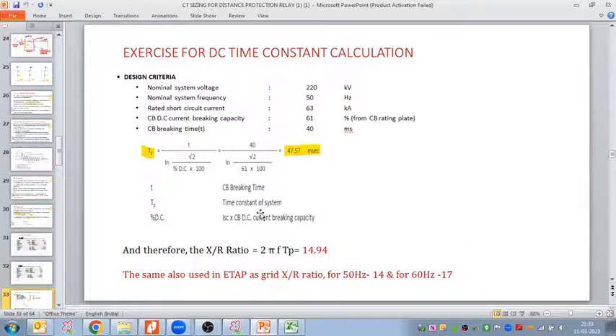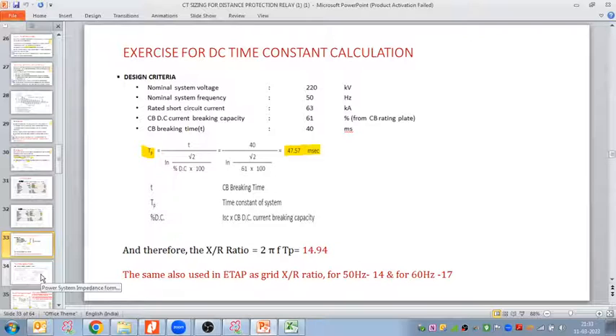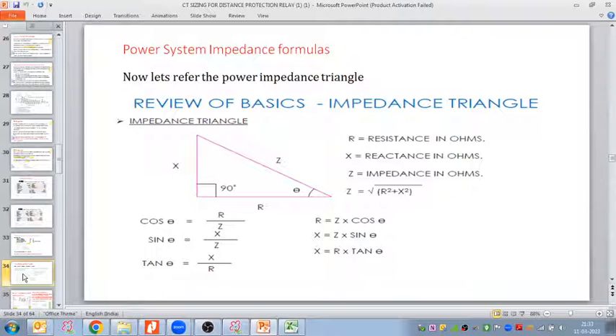So here we discussed the time constant, and based on the time constant we calculated the X/R ratio of the grid, which comes to 14 for 50 Hz, and for 60 Hz it comes to 17. Now based on this X/R we can calculate the source resistance and source reactance. Before coming to the calculations, let us quickly review the power impedance triangle which we studied during college time.